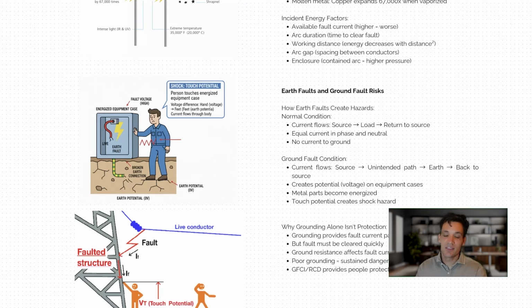Now, in a properly designed system, when the frame is connected or bonded to earth, when the fault occurs, current flows through the frame into the earth conductor, which should have sufficient current that causes the circuit breaker to trip. If the equipment isn't earthed, when the live wire touches the frame, there will be no fault current because it won't be able to flow to ground. And it'll sit there at 240 volts, whatever it is, until somebody comes along, touches the frame.